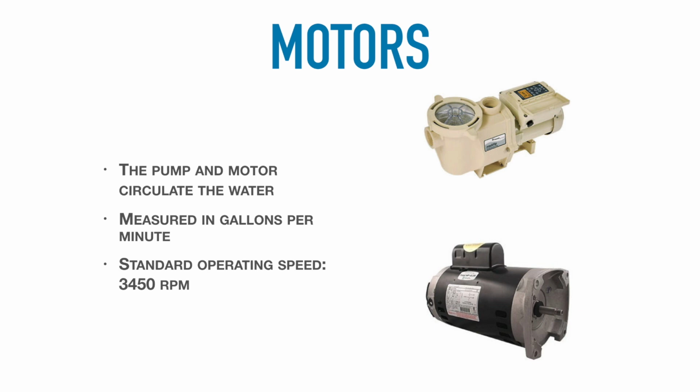Now let's look at dual speed. With a dual speed motor, I'm backing out of my driveway at about 5 miles an hour. Then I'm driving down my street at 5 miles an hour. And then I jump on the highway at 75 miles an hour. Again, not ideal, a little bit better than the single speed, but with variable speed, I can adjust that motor to the speed that I need exactly. And as a result, I'm going to draw less amperage, which means I'm going to lower my energy bill in the long run. That's the reason why they're going for these variable speed motors, to lower our energy costs in the long run.